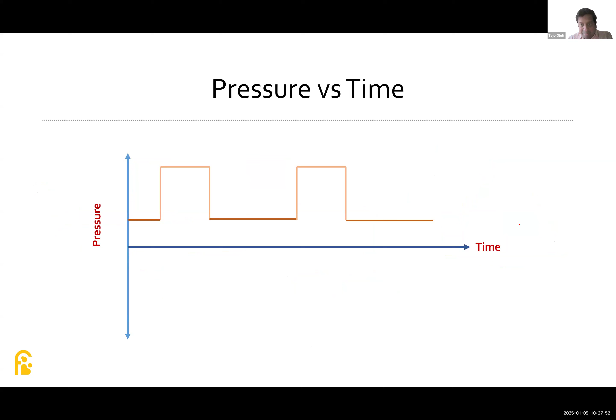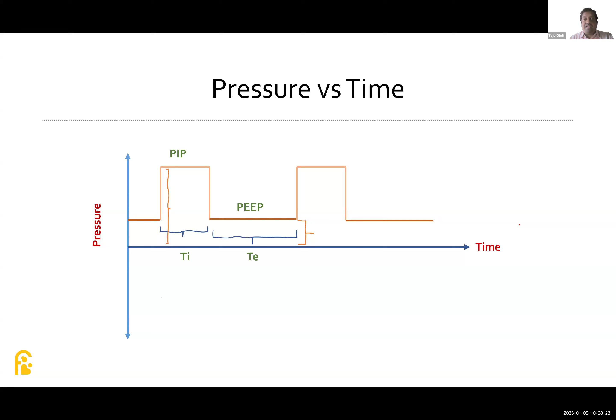So the scalar graphics, as we discussed, first one is the pressure versus time. I have shown you in the previous slide while I was drawing it. So this is how it will appear on the pressure versus time. So this is the peak inspiratory pressure that you measure, and it could be a set pressure in a pressure control mode, and then PEEP, which we keep. That will be there throughout the respiratory cycle. That is the positive end expiratory pressure. The PIP will be delivered only during your inspiration. The PEEP alone will be there during the expiration.